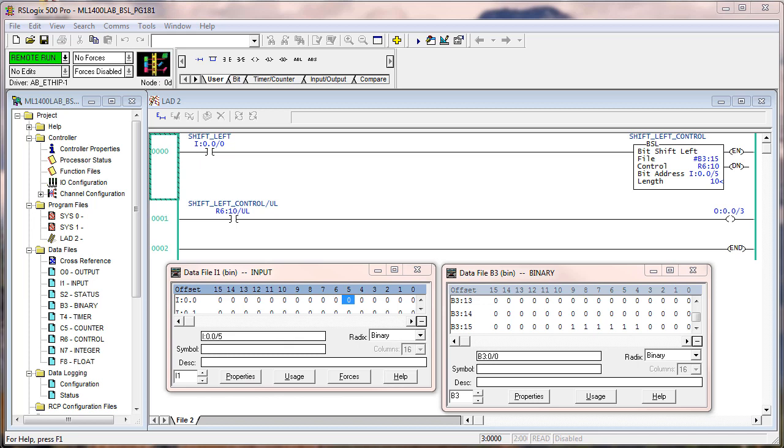If I shift it one more time, because right now it's saying you unloaded a 0. That's the problem, there is a difference between nothing and 0. In this case, we're talking about 0 or off, not nothing. So typically you look at zeros and you think there's nothing there. Well, that 0 right now at bit 10 of B315 is significant. It is the state that was shifted from bit 9 to bit 10.